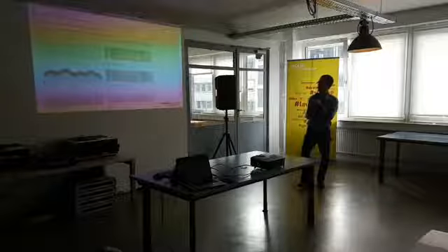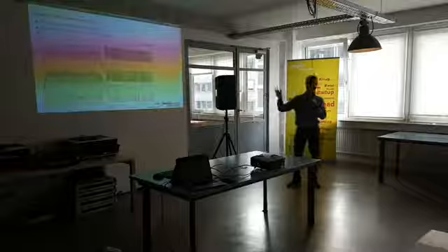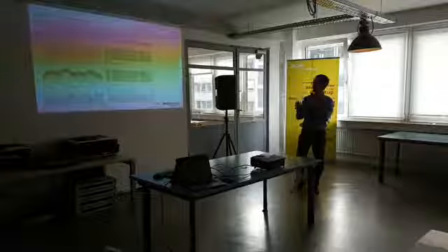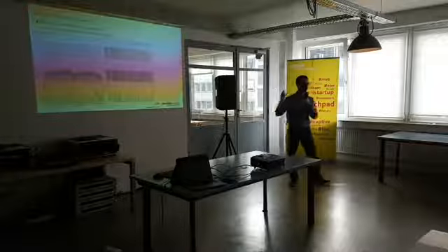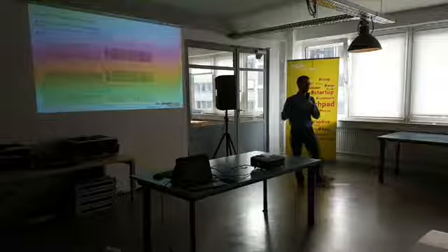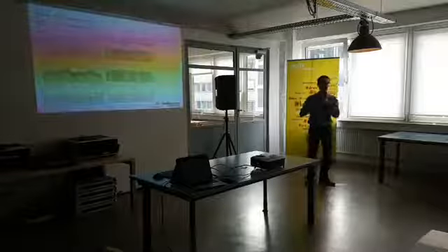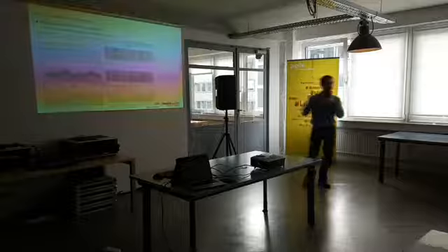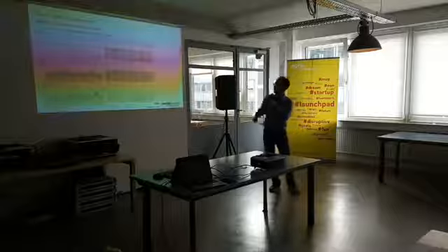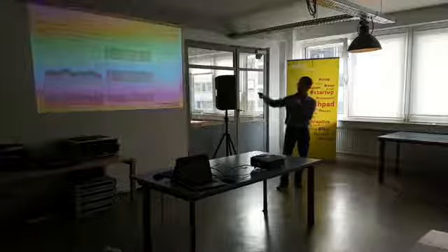Now I show you instead larger time windows, similar measurement devices. This is the online interface of our online Scala. On the upper two plots are voltage magnitude and phase angle. The phase angle is a little messy because the measurement is over 2 hours, and since frequency is not constantly 50 Hz, the PMU measures phase angle rotations. Over 2 hours you get a lot of phase angle rotation due to the frequency being, say, 50.01 rather than 50. The second row shows current magnitude and phase angle, and the third row shows frequency and rate of change of frequency.